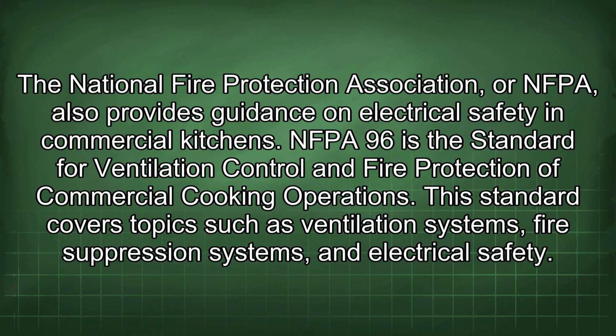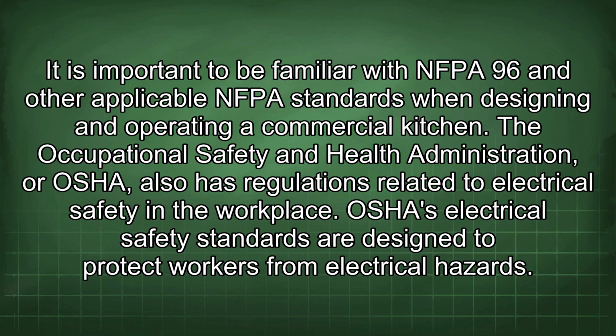The National Fire Protection Association, or NFPA, also provides guidance on electrical safety in commercial kitchens. NFPA 96 is the standard for ventilation control and fire protection of commercial cooking operations. This standard covers topics such as ventilation systems, fire suppression systems, and electrical safety. It is important to be familiar with NFPA 96 and other applicable NFPA standards when designing and operating a commercial kitchen.